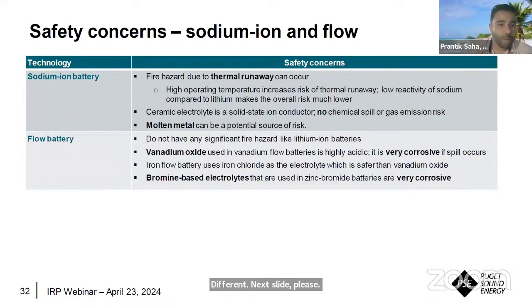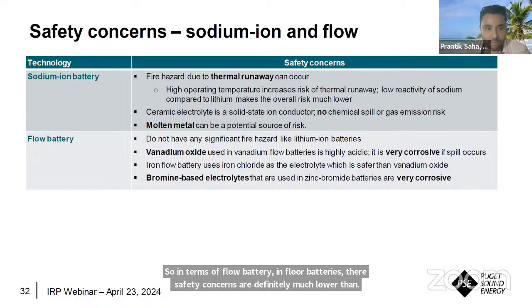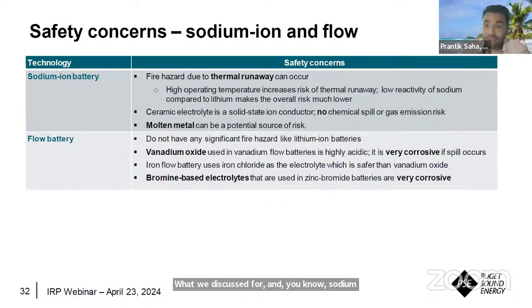In flow batteries, safety concerns are much lower than what we discussed for lithium-ion and sodium sulfur batteries - for example, there's no thermal runaway. Most safety concerns come from the fact that the electrolytes used are reactive and can be corrosive. Vanadium oxide is a little corrosive, damaging pipes and valves. Iron flow batteries are less corrosive than vanadium oxide, but since it's a salt, you can get salt deposition in the valves, blocking pathways.